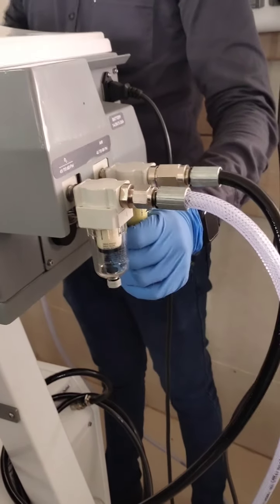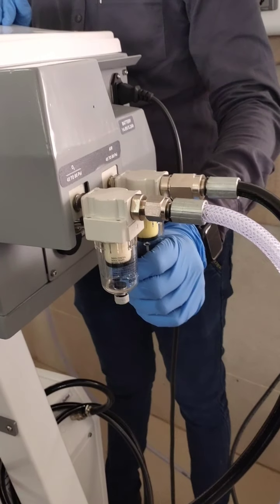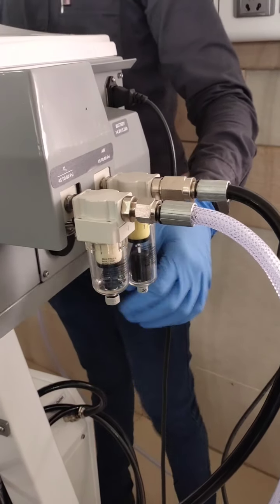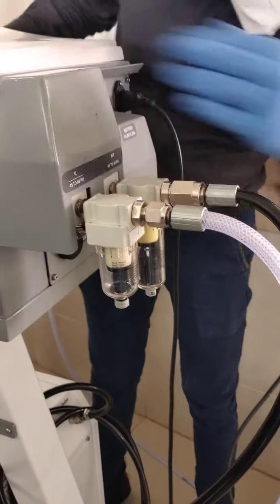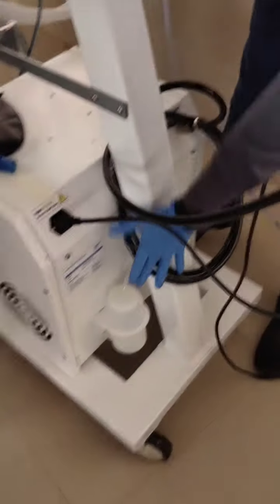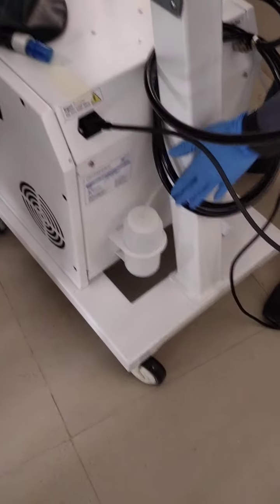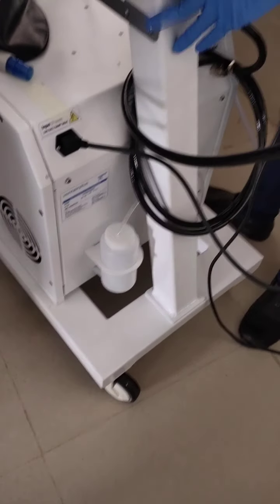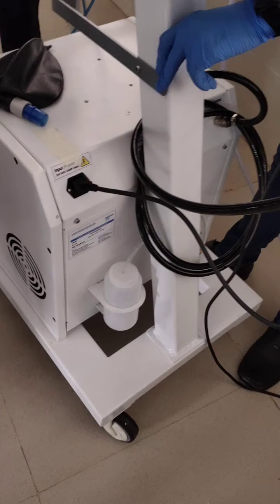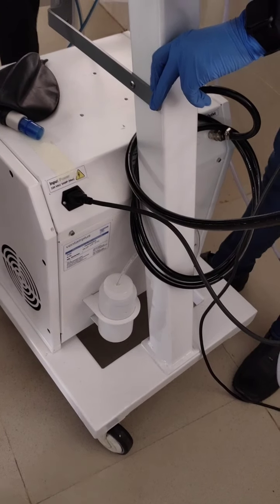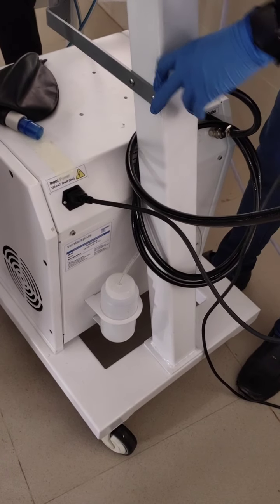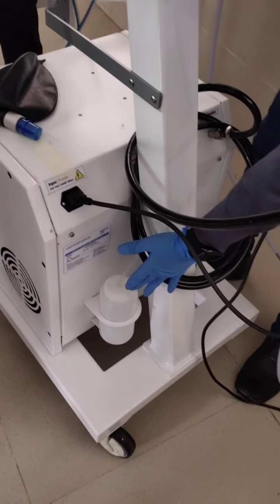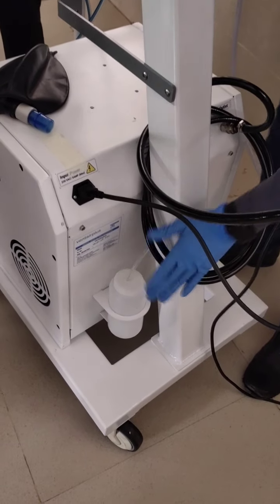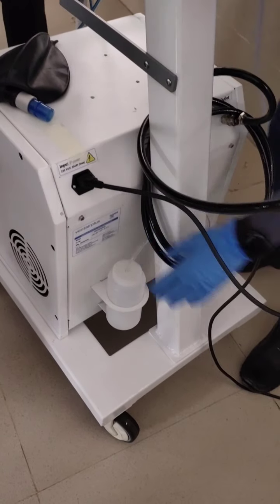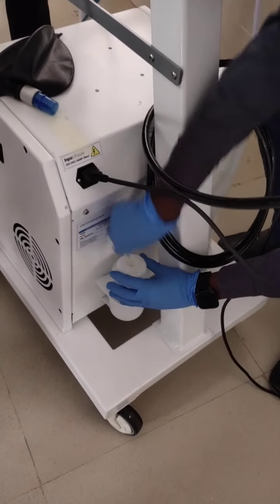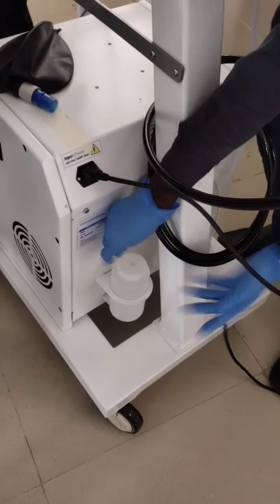Suppose an error comes, like the pressure is not enough, so the air is switched to oxygen. And in the air compressor we also have a waste bottle. Here also some moisture will come in that air. If the humidity in our ICU ward is high, the cooling air will convert it into water, and that water will drop here. If this bottle is full, you have to clean it. You just take it out, open it and dispose. Okay.